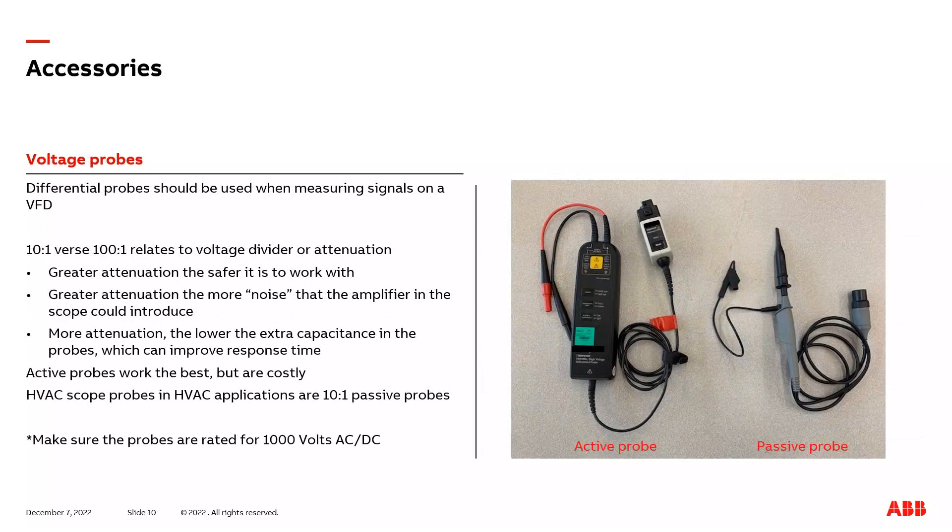Once the scope has been selected, it's time to think about accessories to go with the scope. We'll first talk about voltage probes. Since a VFD's DC bus and output waveform are not referenced to earth ground, we'll want to select a differential style voltage probe. Now, one of the first spec items you may notice when looking at different voltage probes is, is it a 10 to 1 or 100 to 1? All that means is how much is the incoming voltage divided by before it's inputted into the scope. If it's 480 volts divided by 10, it's 48 volts. If it's 480 volts divided by 100, it's 4.8 volts that's inputted into the scope. Obviously, the greater the attenuation, you would say, that's safer to work with.